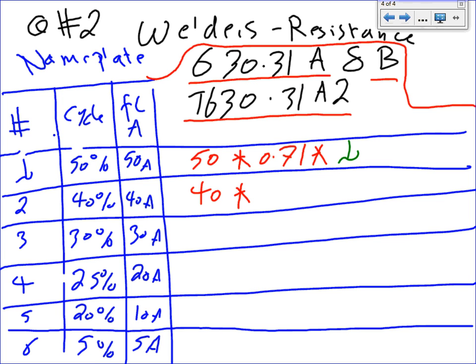Right, guys? 0.63. Correct me if I'm wrong here. 0.63 times. Okay, now, if you read B, B tells you to take the largest at 100%, everything after the largest at 0.6. So this will be 0.6. Is it right? Yes, sir. Can you show me where it says the first one at 100%? Read B.